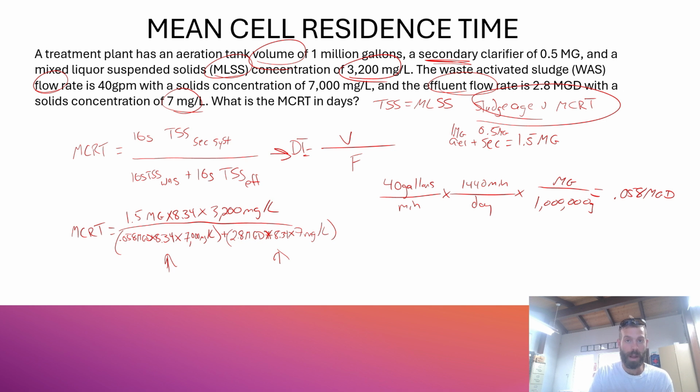If it's younger, you're probably not doing very much aside from BOD, like 2-3 days. You're probably just doing BOD TSS removal. If you're doing 11, 12, 13 days, you're doing biological nutrient removal. Okay, you're nitrifying, you're denitrifying, these kinds of things. If you find yourself in a conventional activated sludge plant and your MCRT is 11 days, you need to waste more. If you find yourself in a BNR plant and your MCRT is 3 days, you need to waste less. That kind of stuff, okay?